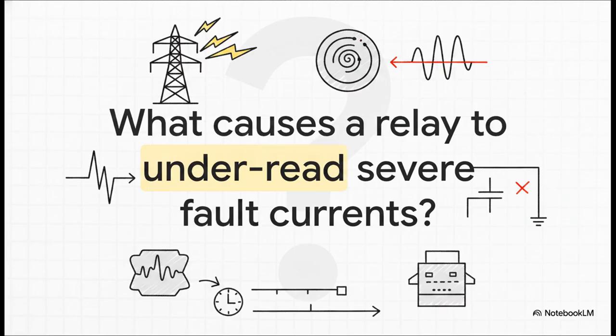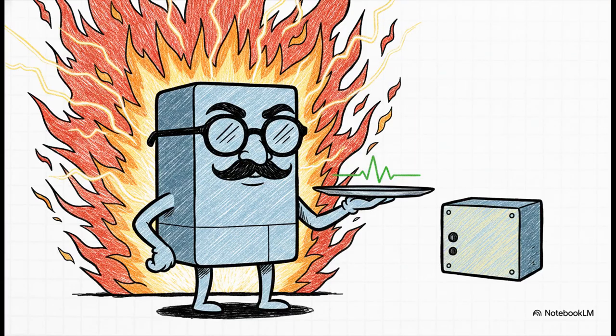Okay, let's do a quick knowledge check to lock this all in. Imagine you're reviewing a fault report. A relay underreads a severe, close-in fault with a high DC offset, causing a dangerously delayed trip. What is the likely cause of the sensor failure? If you said CT saturation, you hit the nail on the head. That heavy DC offset drove the iron core of the current transformer right into saturation, the waveform flattened out, and the true severity of the fault was essentially masked from the relay, forcing that delayed trip.